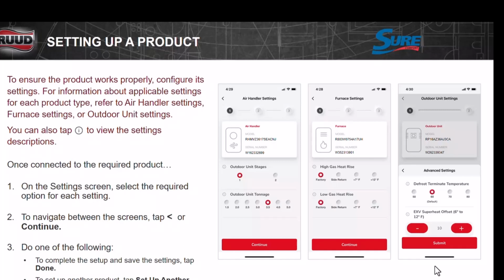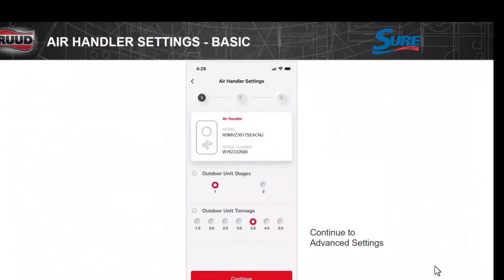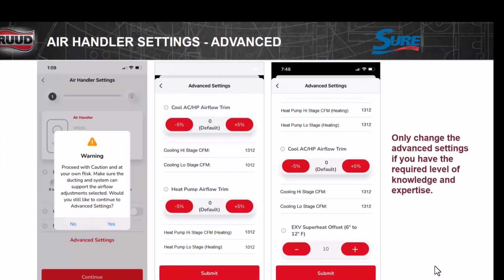If you add an EEV there, you can adjust the EEV on the outdoor unit. You can adjust the subcooling. I would leave that where the factory set it. On the air handler, we can do the same type of advanced settings. One of the nice things about this one is, once you go into the advanced settings, you're going to get this warning code. Basically what it's telling you is, if you don't know what you're doing, don't go there, right? So you say yes, you get in there. Now you can adjust your cool trim, your heat pump trim on that unit.